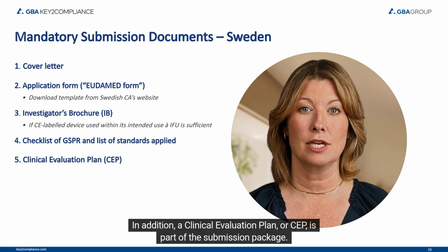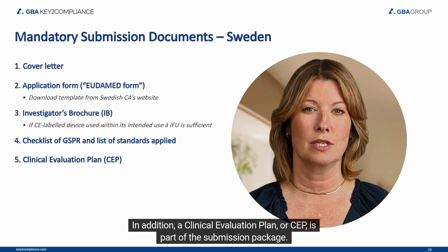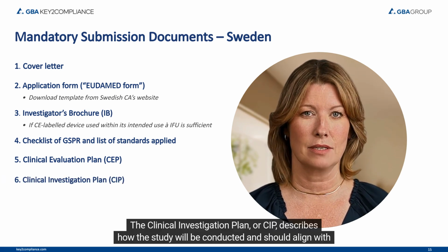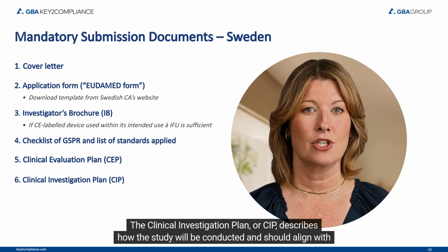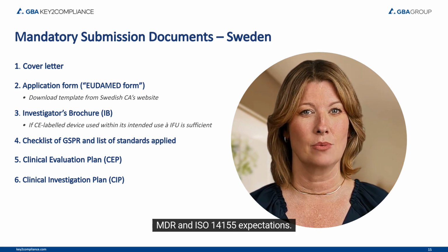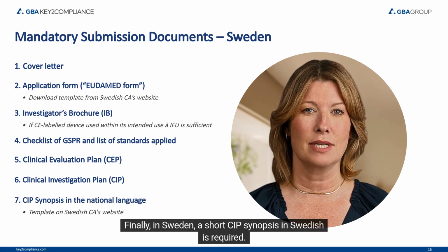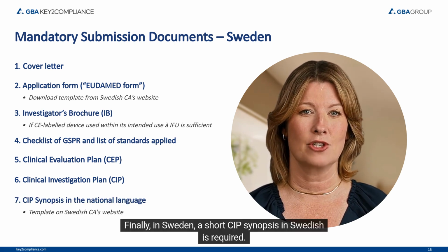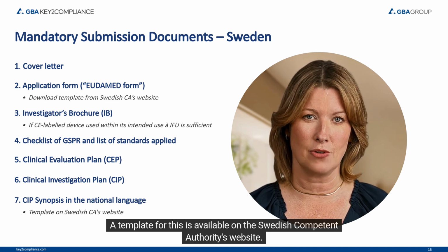In addition, a clinical evaluation plan, or CEP, is part of the submission package. The Clinical Investigation Plan, or CIP, describes how the study will be conducted and should align with MDR and ISO 14155 expectations. Finally, in Sweden, a short CIP synopsis in Swedish is required. A template for this is available on the Swedish Competent Authorities website.